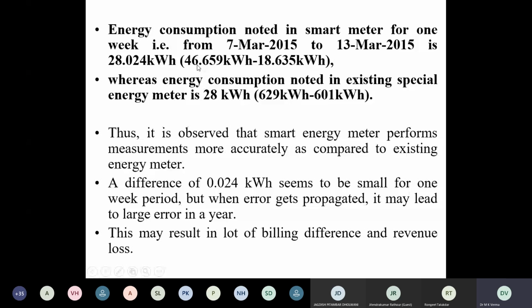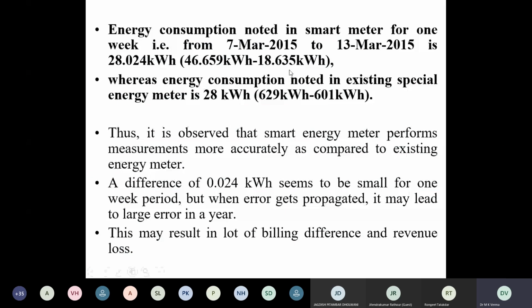The final reading was 46.659 kilowatt hour and the initial reading was 18.635 kilowatt hour. With the special energy meter, the final reading was 629 and the initial reading was 601. So he got total energy consumption based on the smart meter at 28.024 kilowatt hour, whereas based on the special energy meter it came to 28 kilowatt hour. So there was a difference of 0.024 kilowatt hour. This difference seems small if you consider a one week period, but if you consider the whole year, you have to multiply it for the whole year. This is for one week.